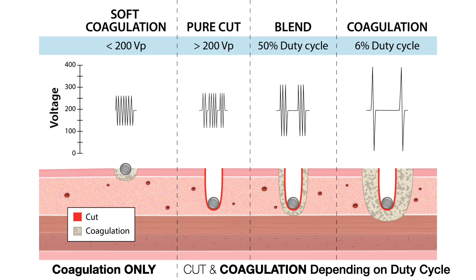Here, less than 200 peak volts results in soft coagulation. You can see this is used for hemostasis as well as for ablation of the edges, if you want to ablate the edges after resection of a large polyp. On the other hand, if you increase the voltage to above 200, it results in a cut. If you create interruptions in the cycles, either a 50% duty cycle or a 6% duty cycle, depending upon how long you interrupt, during that interruption the tissue cools down and that slow heat results in more coagulation. So we've learned about peak voltage, cut, coagulation, soft coagulation, and also learned a little bit of duty cycle.